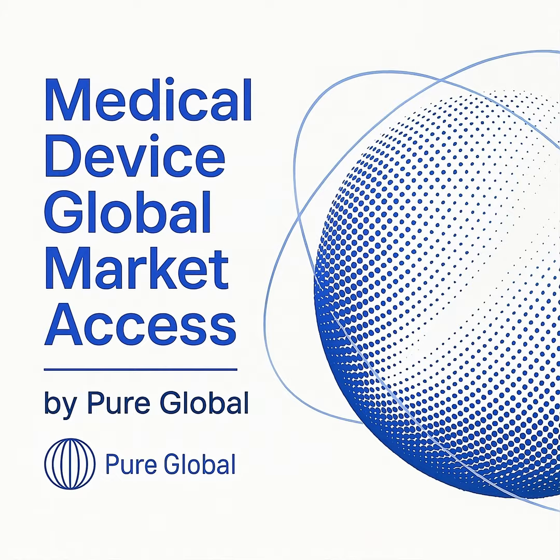They manage the communication for Field Safety Corrective Actions, or FSCAs, which include product recalls or advisory notices. They must also maintain access to the device's technical documentation, ready to provide it to authorities upon request for an audit or investigation. A common strategic mistake we see is manufacturers appointing their commercial distributor as their in-country representative.